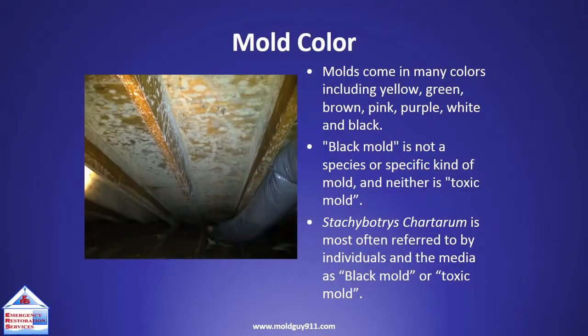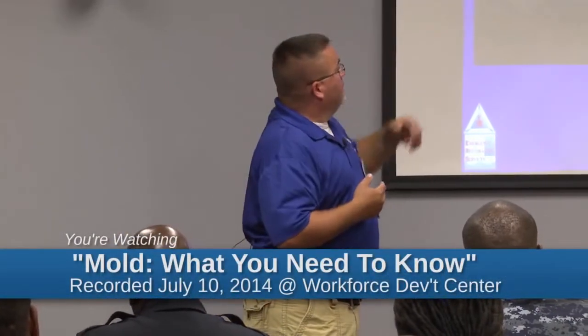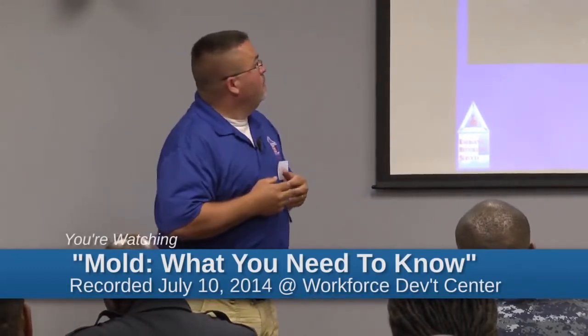This is another example, in an attic space. It's kind of hard to tell, but there's actually a lack of insulation at the ceiling level. This was in the middle of winter, so you had a really cold attic with no insulation between the living space and the attic space, and that heat and moisture was coming up through the drywall. It was hitting the cold plywood and cold framing of the attic, causing condensation, and once again causing a wide-scale mold problem. And this is actually from the client that I was telling you about with the aspergillosis.